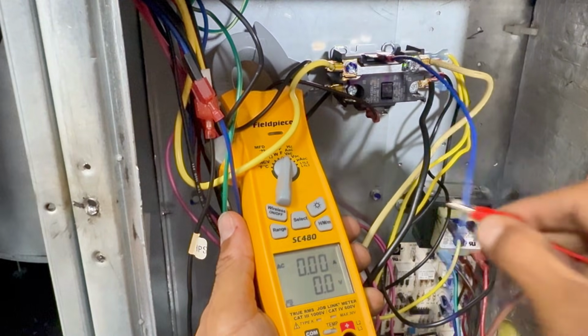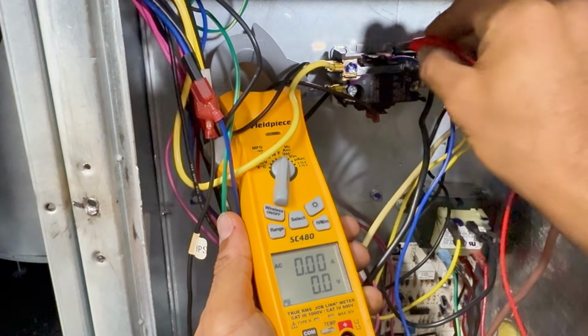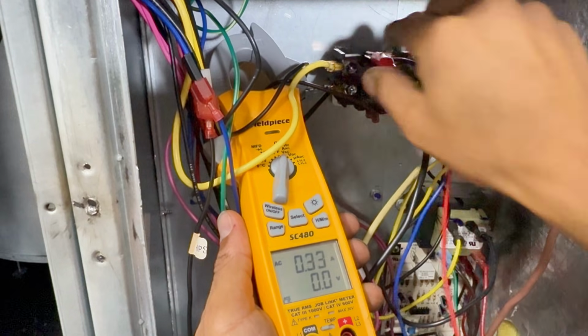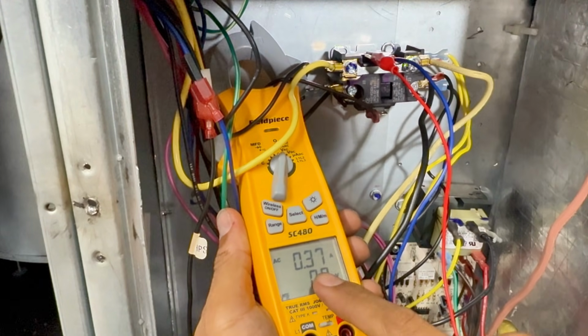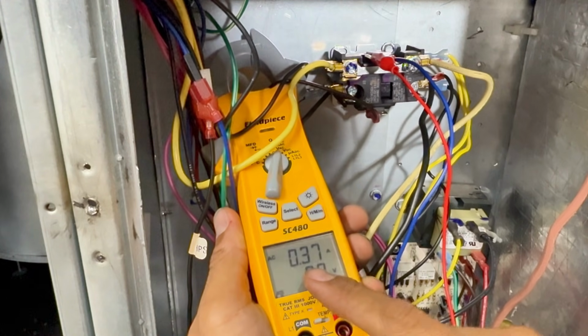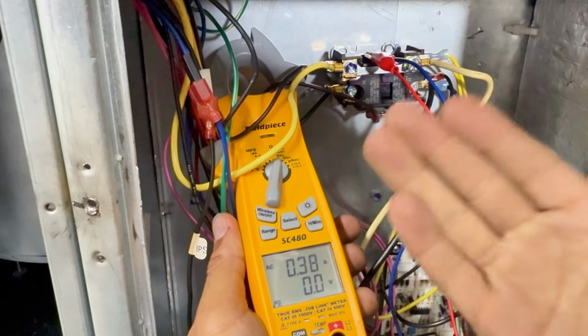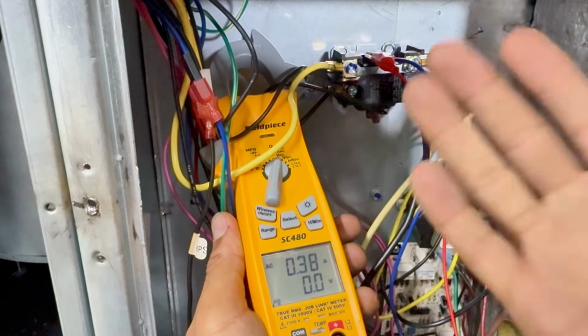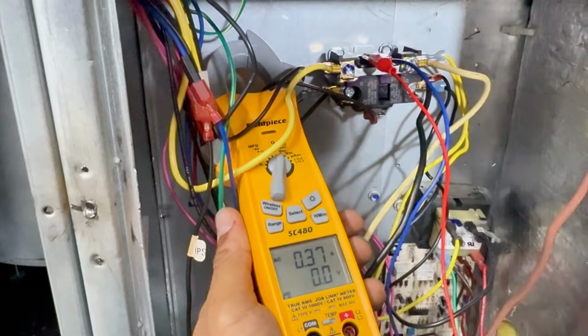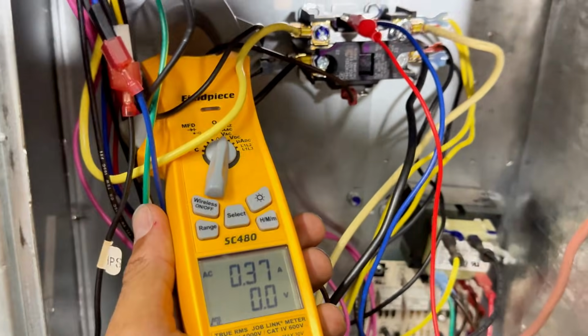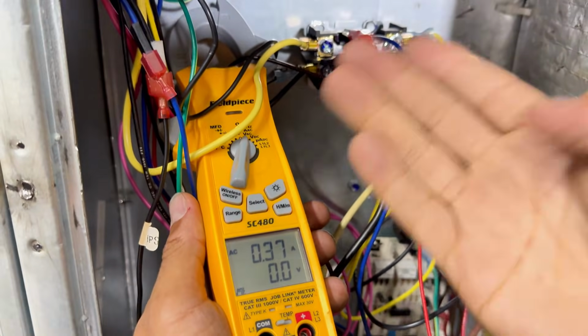So I'm gonna go ahead and power it up. Keep an eye on that. I'm gonna send 24 volts right now. Okay, look at that. It's pulling 0.37. So it is less than 1 amp, but it's pulling current. And look at that, that switch there, the little push button, that's pushed in. But to confirm, I know that I'm pulling amps.